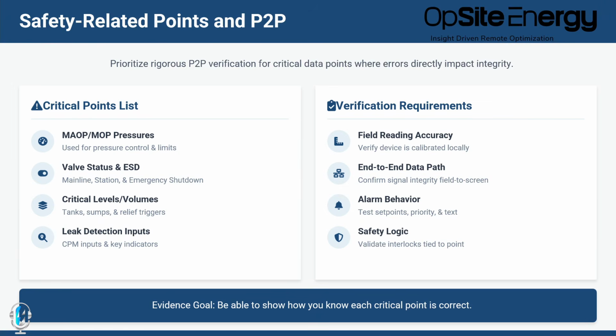Your critical points could be your transmitters providing MAOP or MOP, your valve statuses from ESD, and at a station you have your critical levels and volumes, plus points feeding your leak detection system. It's so critical to make sure this process is set up correctly and is being followed, so you have a good start to these assets when you're bringing them online.